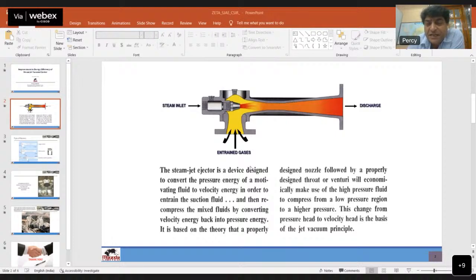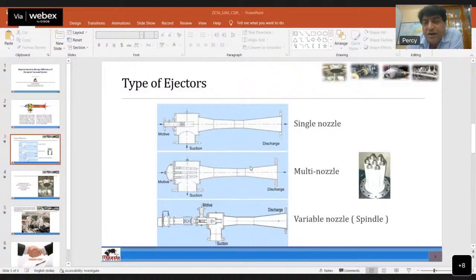But this is a simple ejector. Now what we have developed is different types of ejectors. The first is the conventional single nozzle ejector, which is used everywhere till date. And like in cars, there is multi-point fuel injection, the new one replacing the carburetor. Likewise, in our ejectors, we have developed this multiple nozzle ejector, where the single large nozzle is broken up into 7 small nozzles, and you have 7 sprays of steam coming out of the ejector. And because of the 7 sprays, though small, the cumulative surface area or contact area of the 7 small sprays is more than 15% compared to the large single nozzle spray of steam, and therefore you can entrain more amount of suction vapors, or in other words, you can consume 15 to 20% less steam.